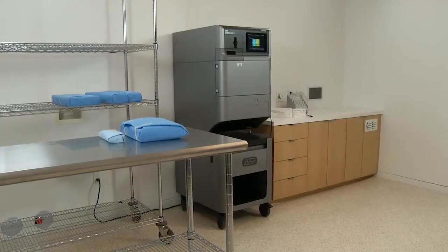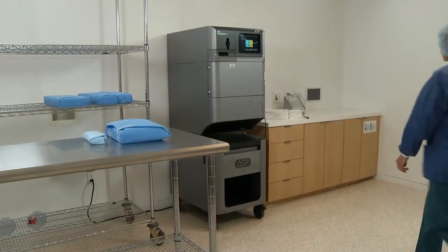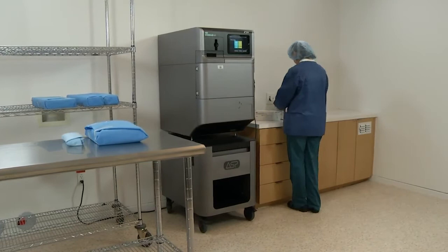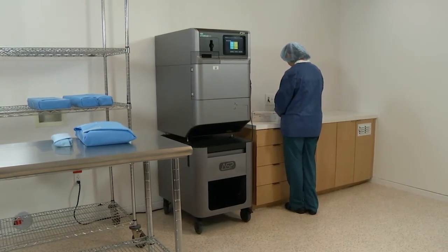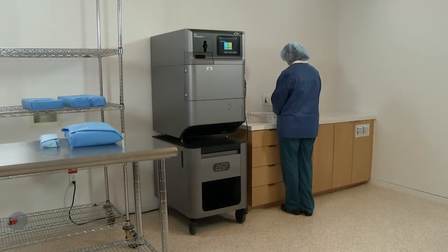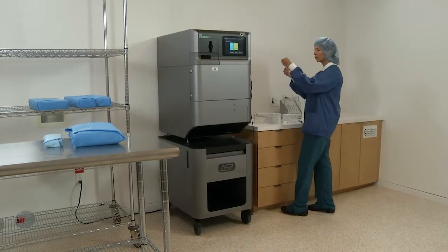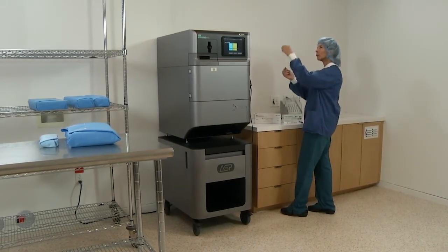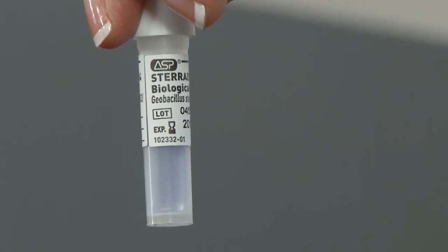Here are the steps needed to process a STERRAD CycleSure 24 biological indicator in the standard and advanced cycles of the STERRAD NX with All Clear sterilizer. Step 1. Assure the BI is at room temperature before use and the growth medium color of the BI is purple prior to use in the sterilizer.